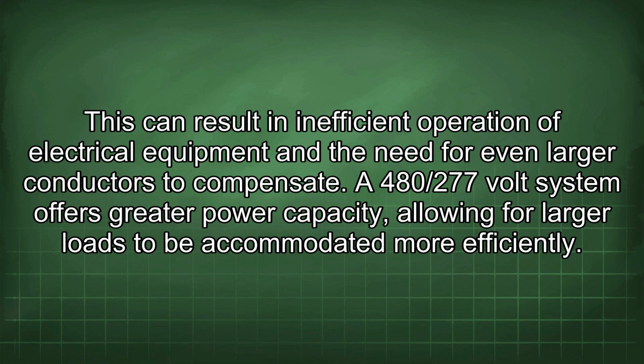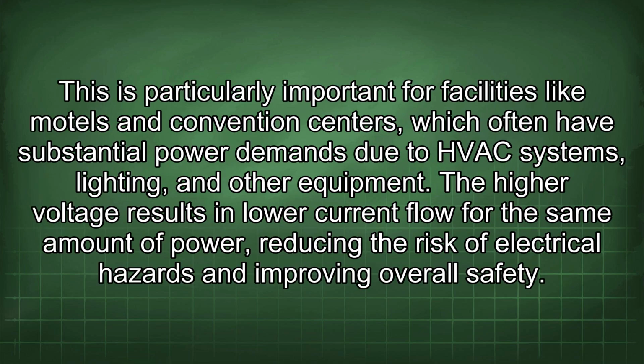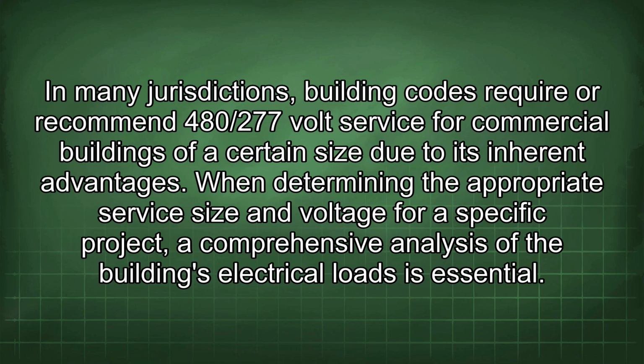A 480/277 volt system offers greater power capacity, allowing for larger loads to be accommodated more efficiently. This is particularly important for facilities like motels and convention centers, which often have substantial power demands due to HVAC systems, lighting, and other equipment. The higher voltage results in lower current flow for the same amount of power, reducing the risk of electrical hazards and improving overall safety. In many jurisdictions, building codes require or recommend 480/277 volt service for commercial buildings of a certain size due to its inherent advantages.